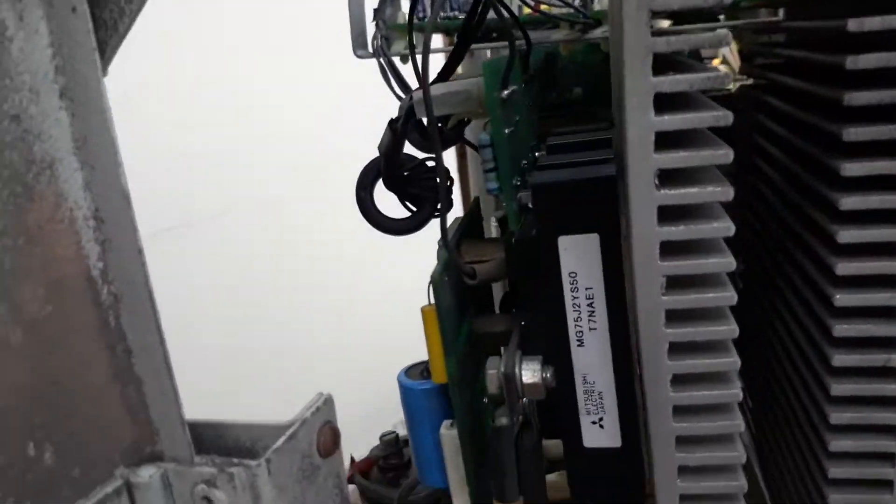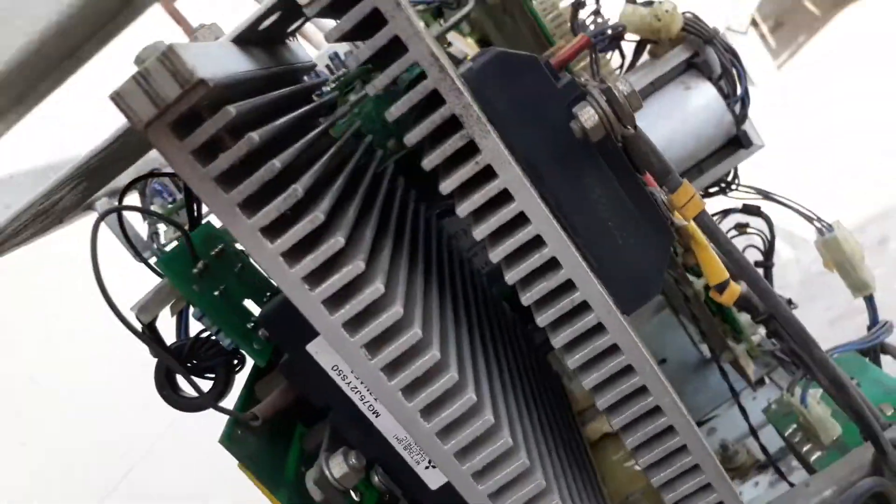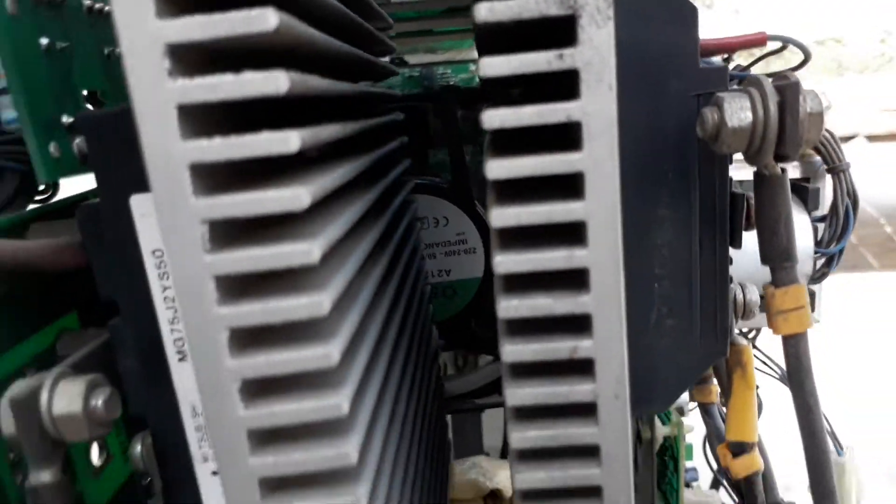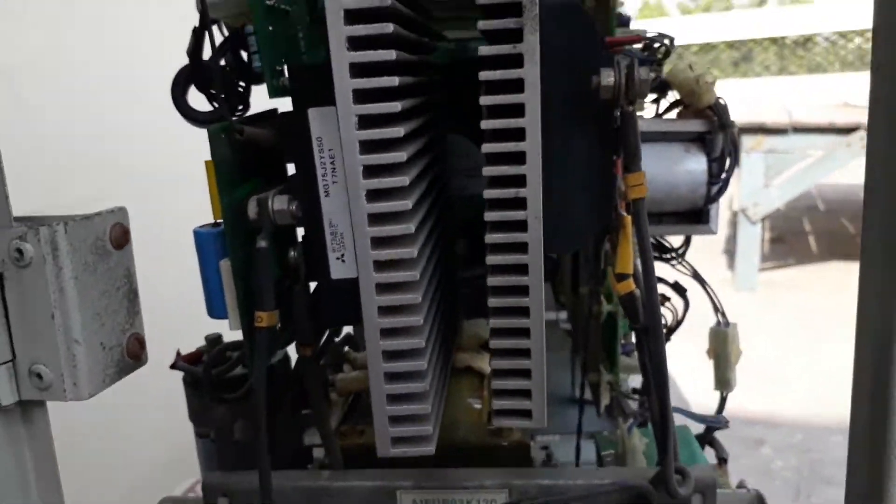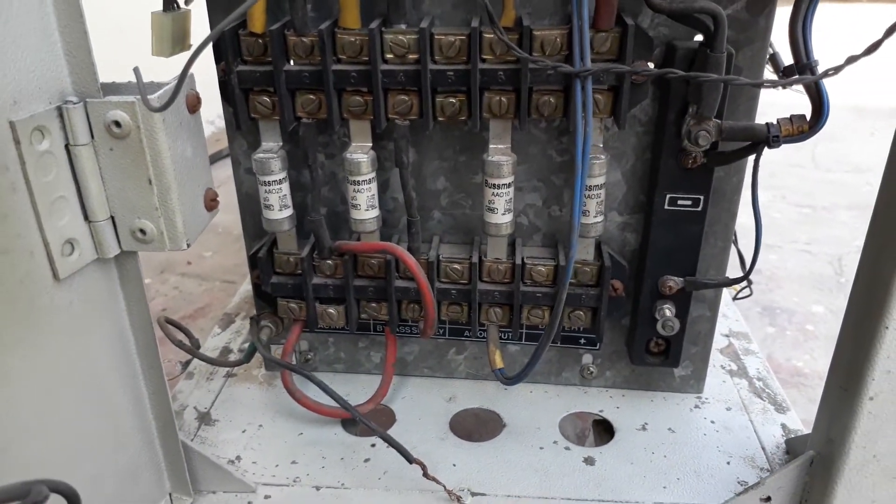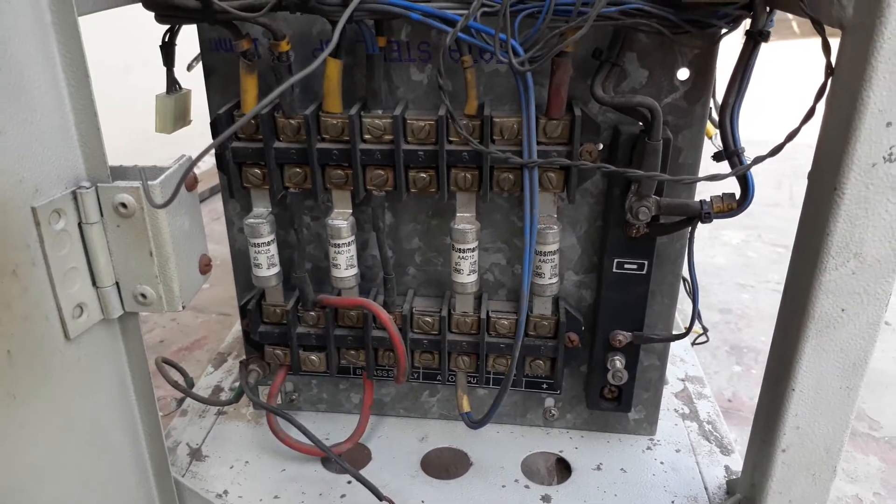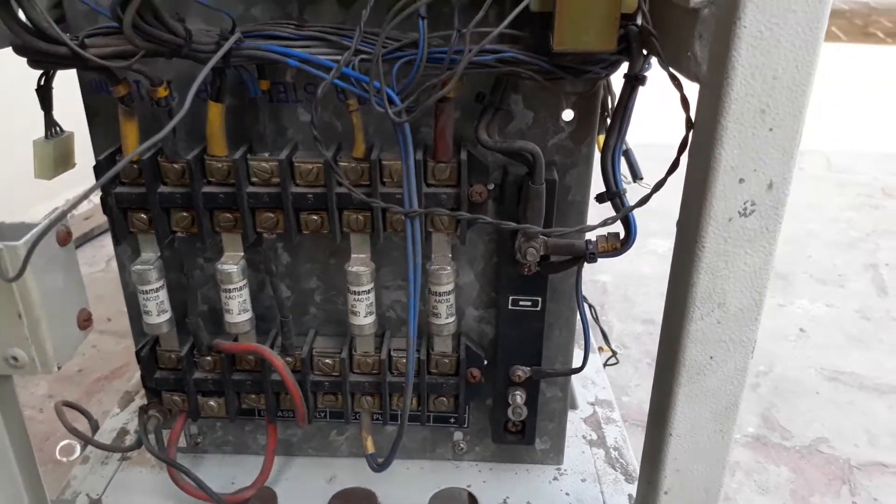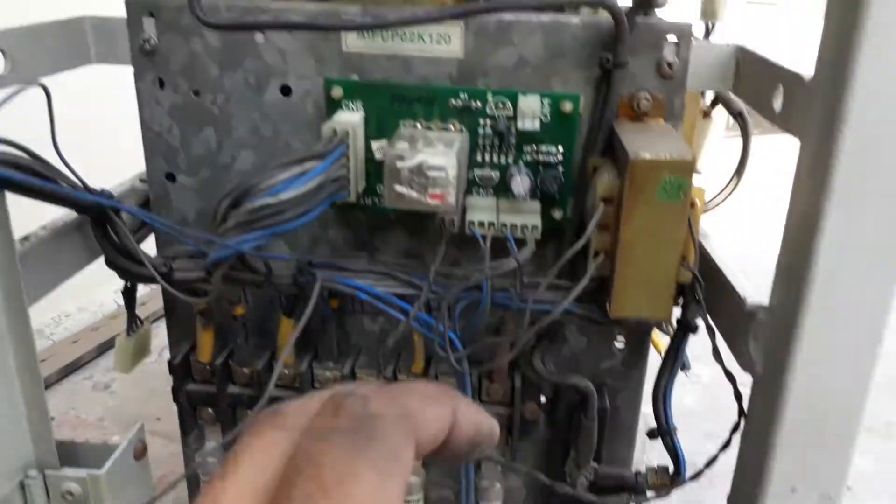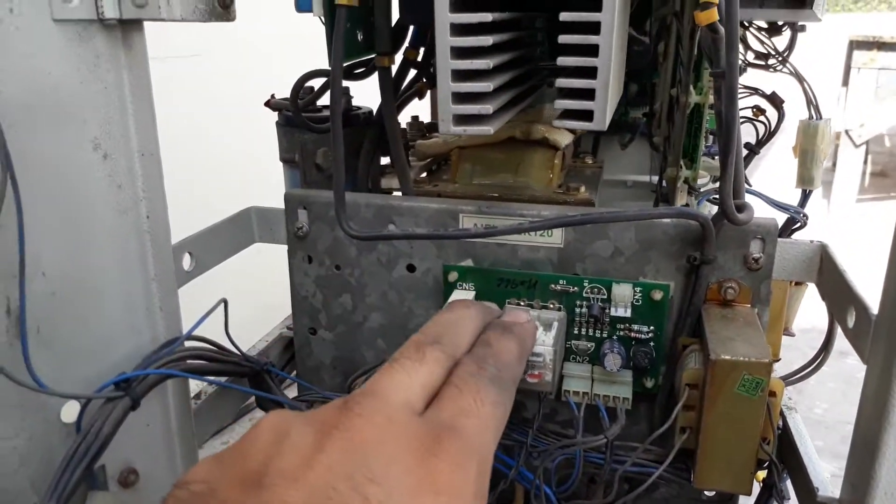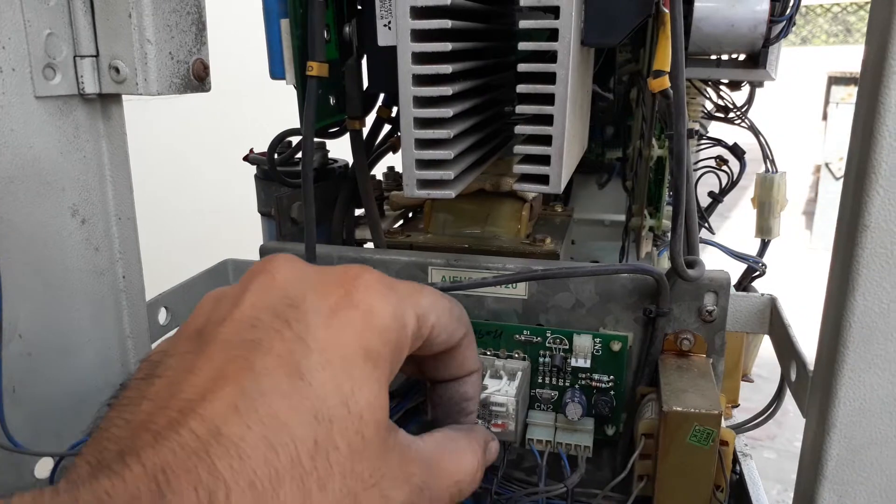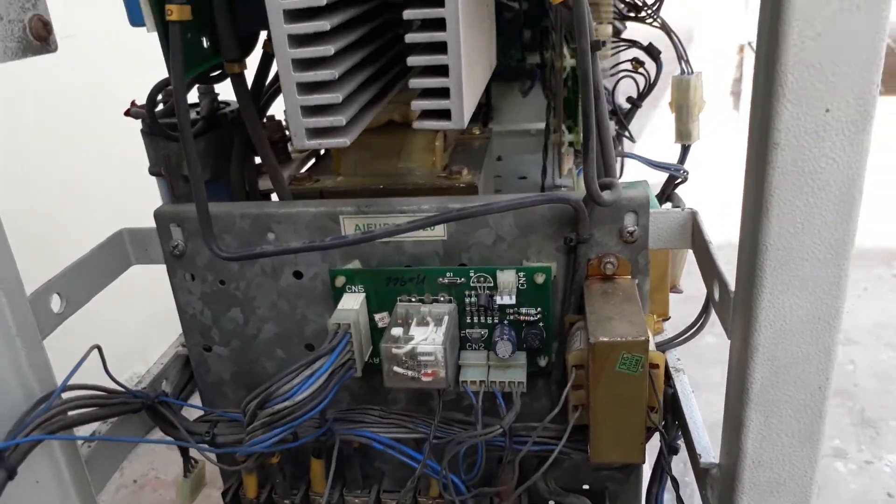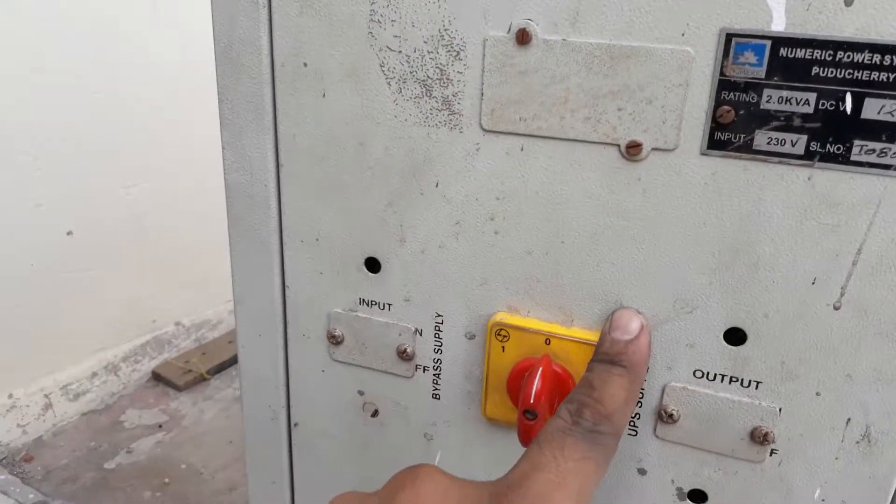Large heat sinks they used, and a fan is also used on the inner side to provide cooling. This is the back view. They provide input voltage, bypass voltage, output voltage, and battery - a common negative point. This card provides bypass voltage.